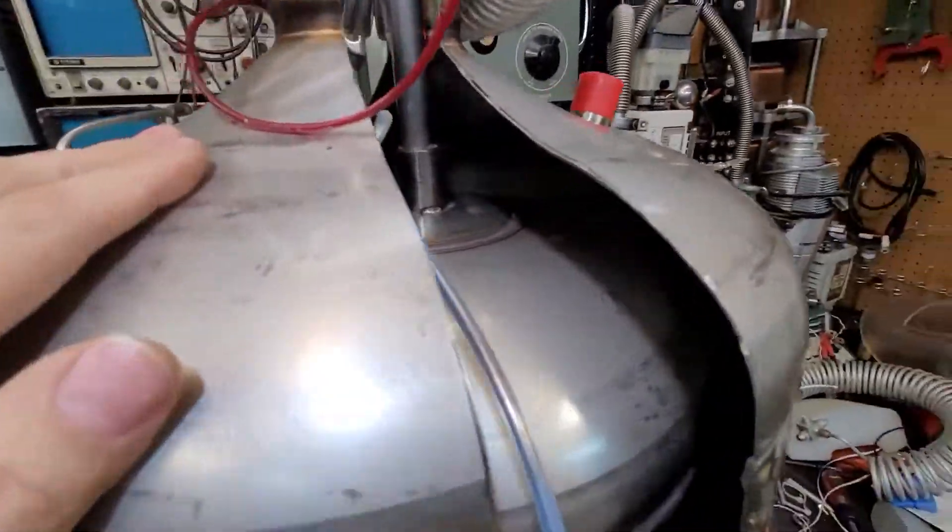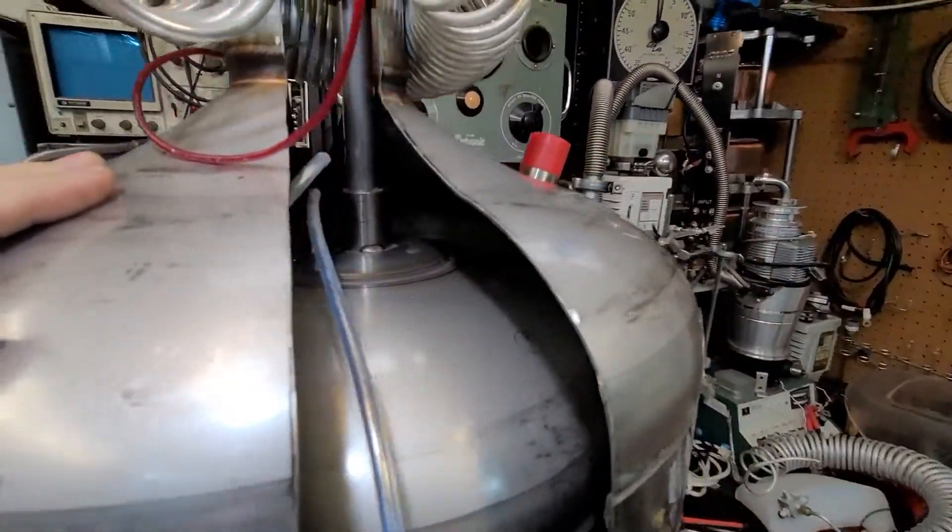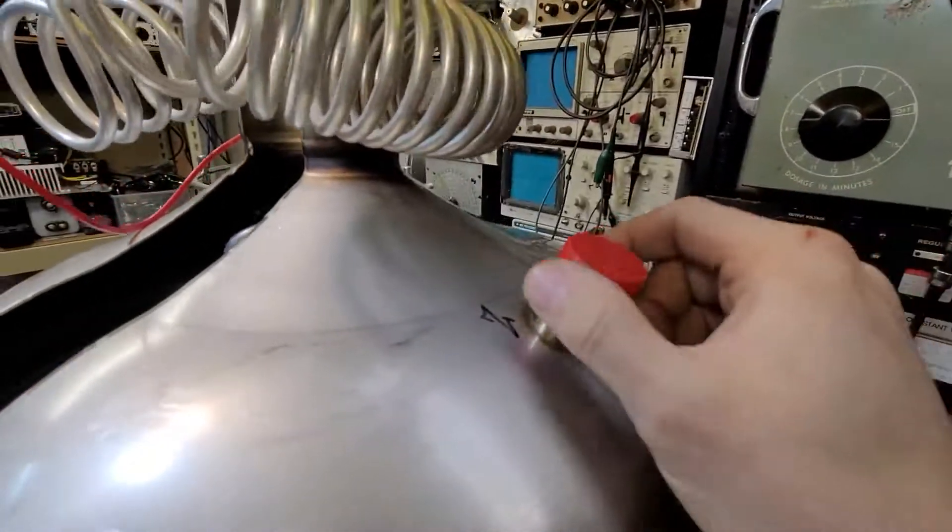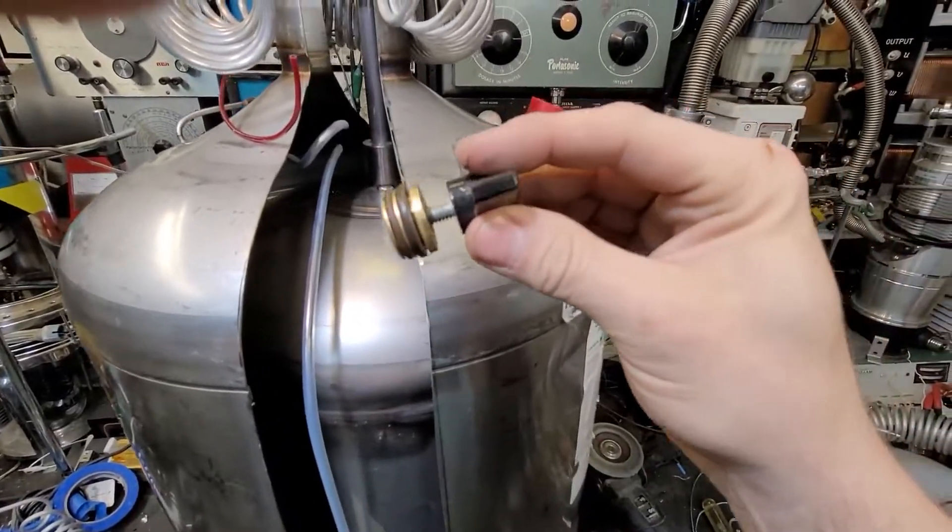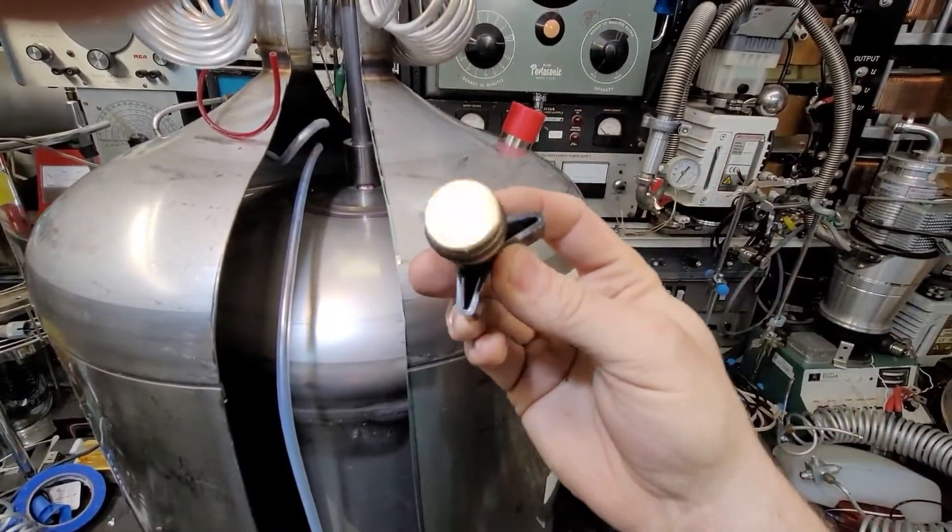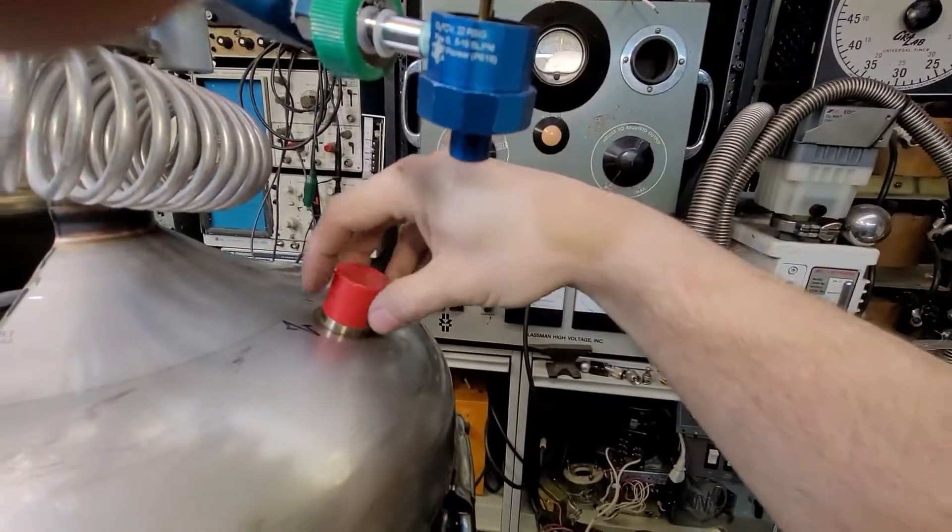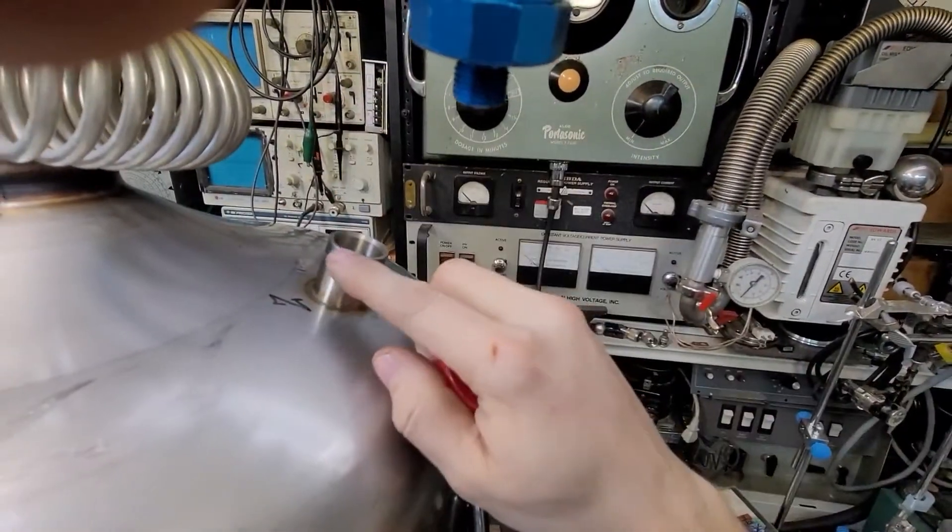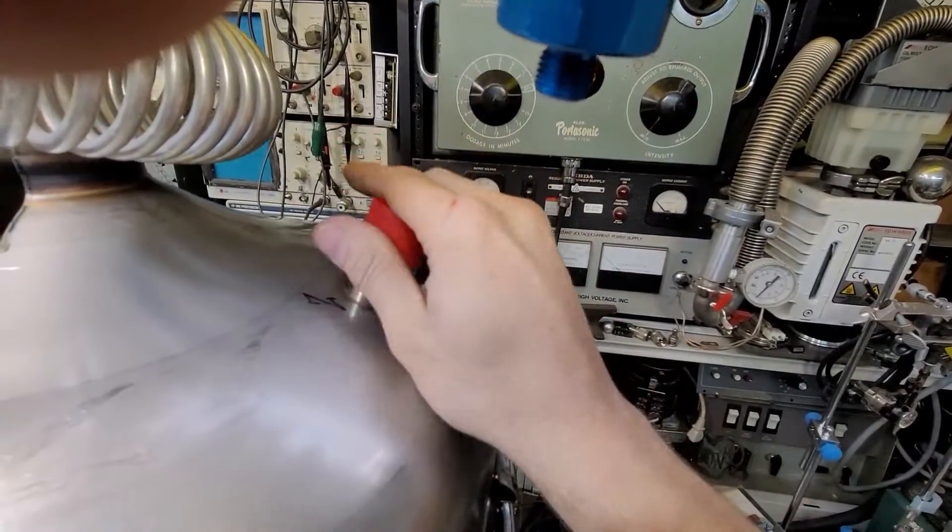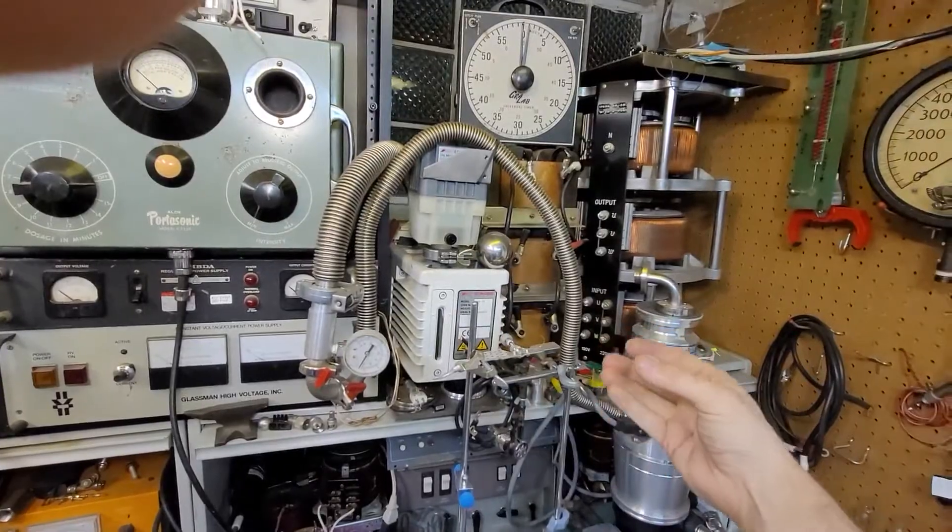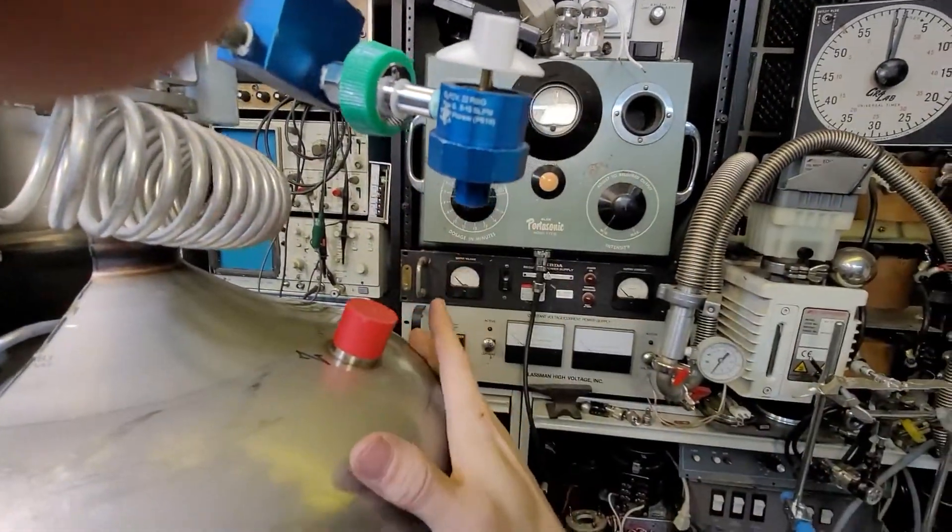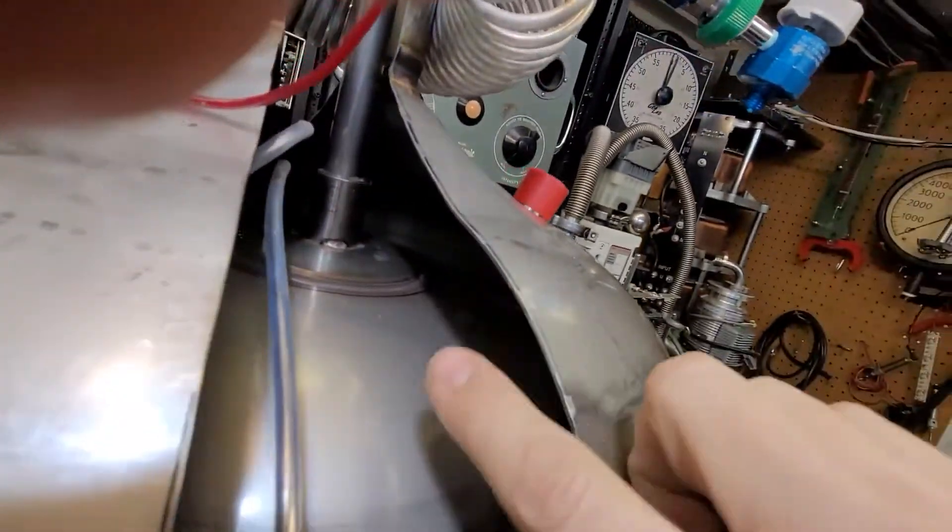So this outer tank here is just a relatively thin wall of stainless. And this plug here is called the vacuum plug. So right now you'll see in there it's just a hole. What lived inside that hole was what's called a vacuum plug, which is this guy right here. So what they do is they hook up a fancy apparatus here or a big tube that clips on. So I can lift this off. And you'll see that there's a little place that it clicks onto some ball bearings. And then they hook up a high vacuum pump like this Edwards RV-12 here. They take the end, they put it on the apparatus and they pump a vacuum. They pull all the air out between these two layers.